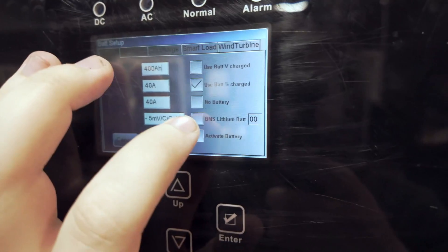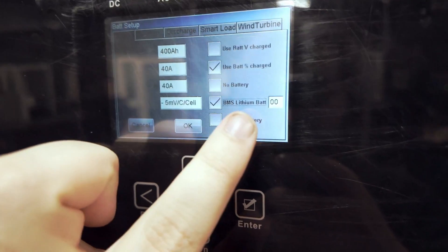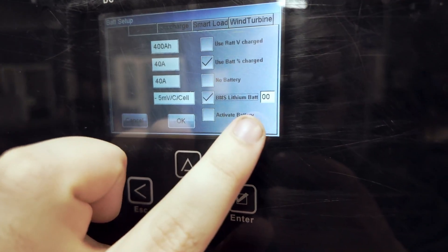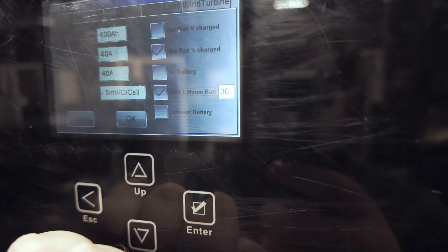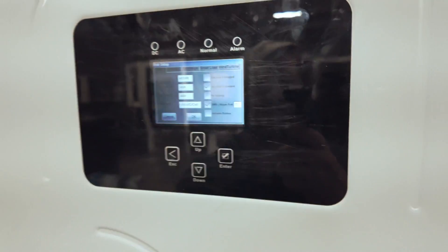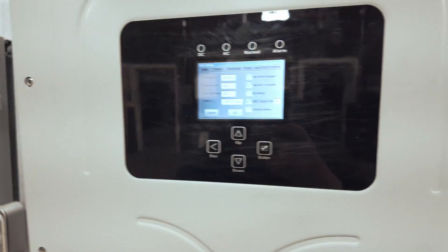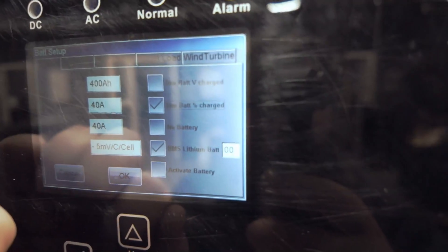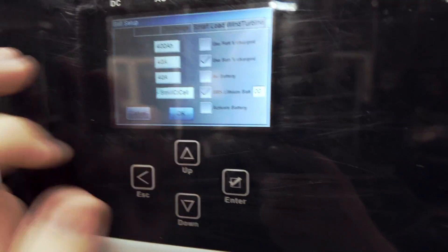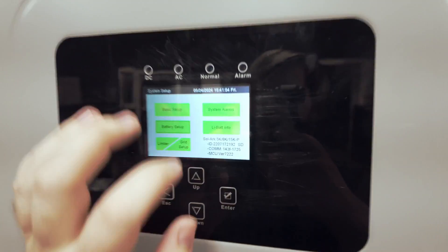Now from here, we will turn on BMS lithium battery and we want the brand to be set to zero zero. It's very important brand is set to zero zero or the communication will not work. We can also do use battery percent state of charge here once you have the lithium communication set up.